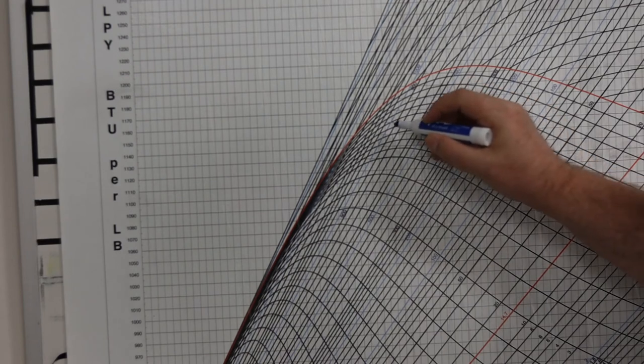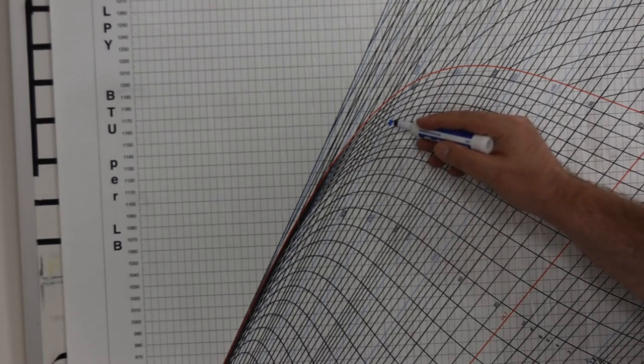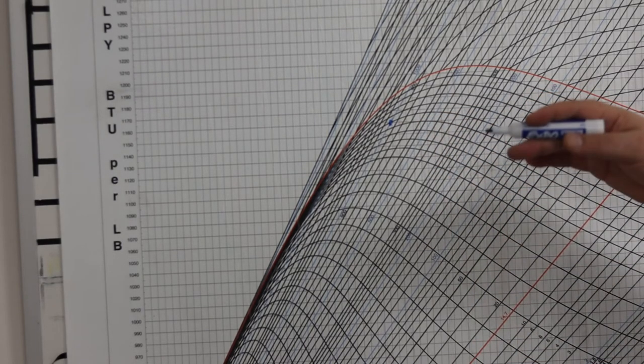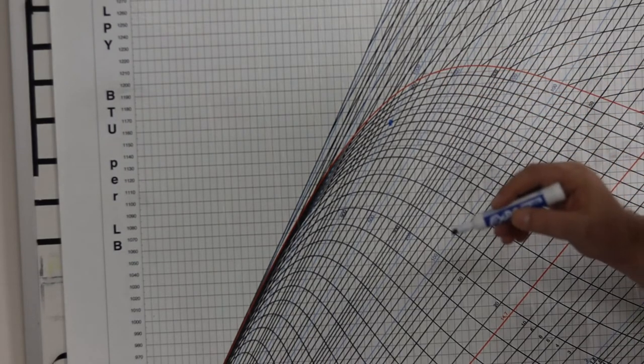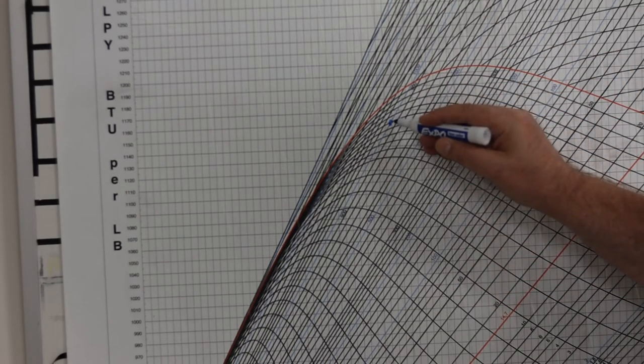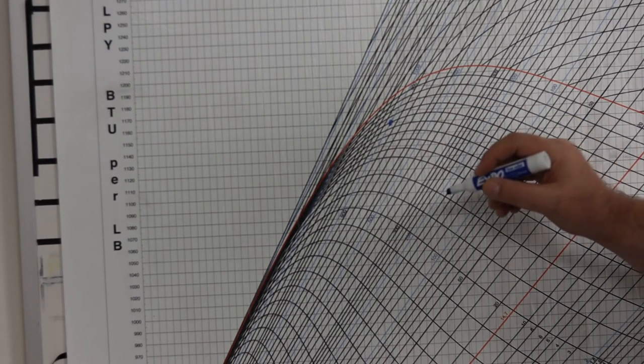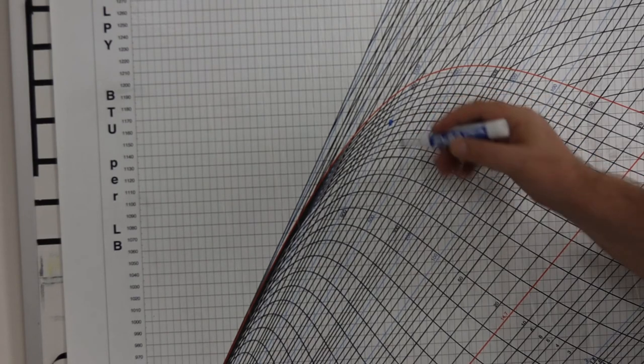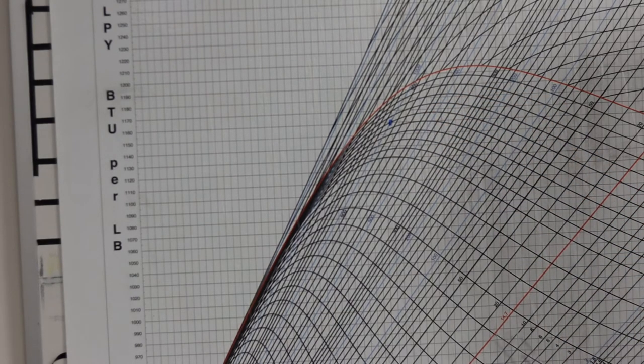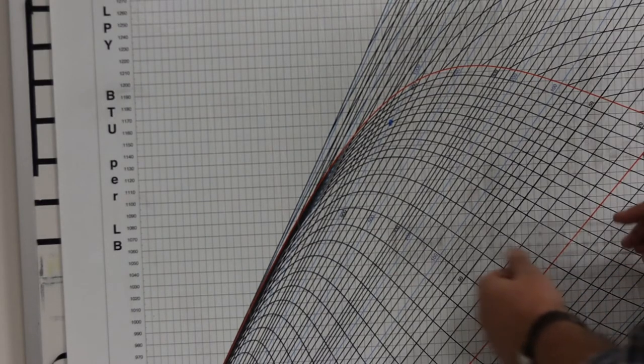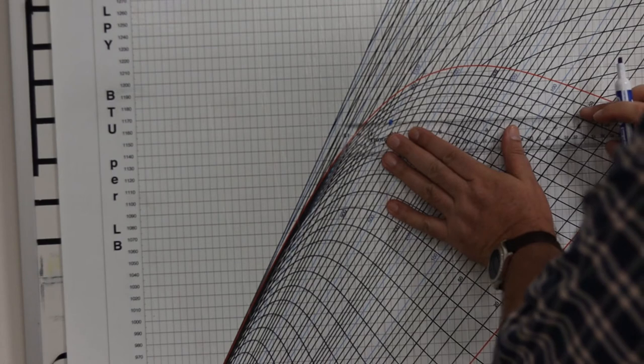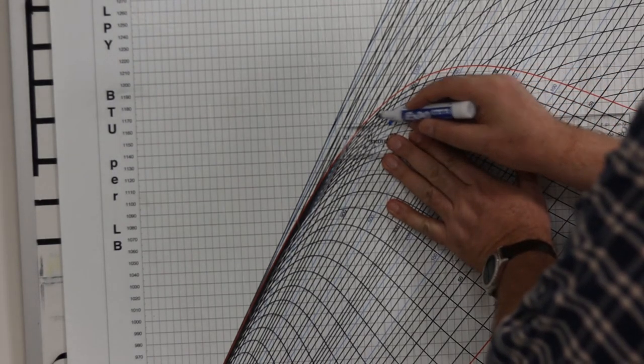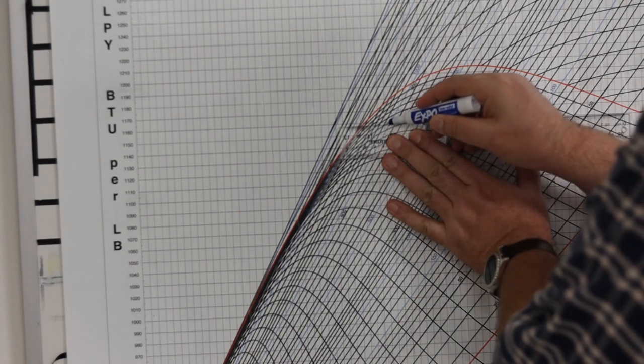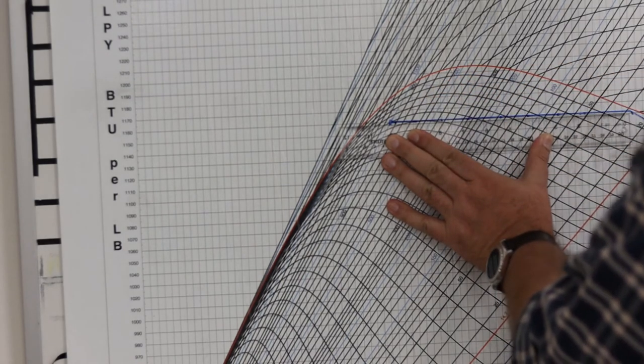we'll say 1,000 PSIA. And let's say that our moisture content isn't real great, it's not real super dry steam, it's not all the way up here to dry saturated steam yet. And we're going to send this steam to another turbine through a valve. Well, a valve is a throttling process, and what that means is it's a constant enthalpy process. So I'm just going to follow that line on the enthalpy of 1160 BTUs per pound mass across.